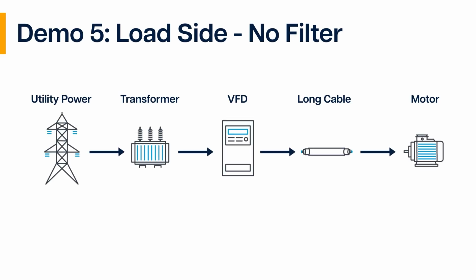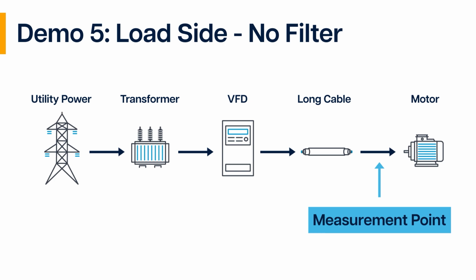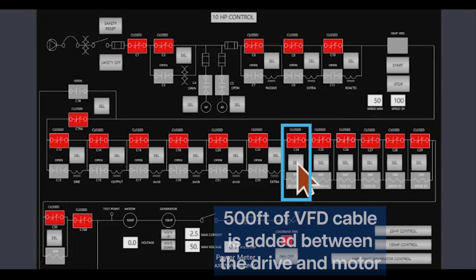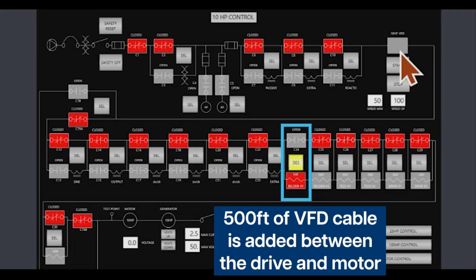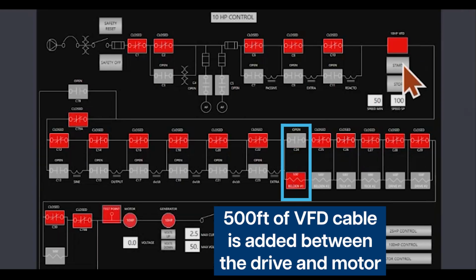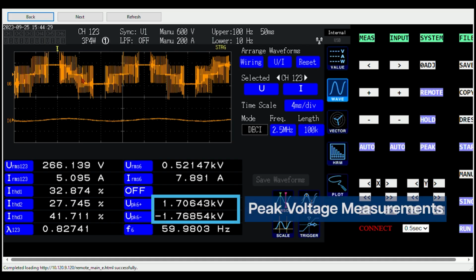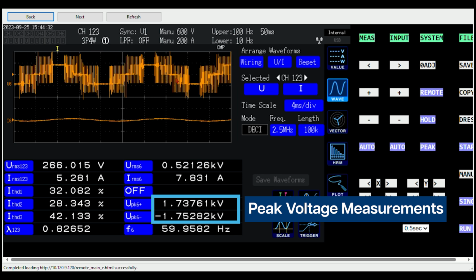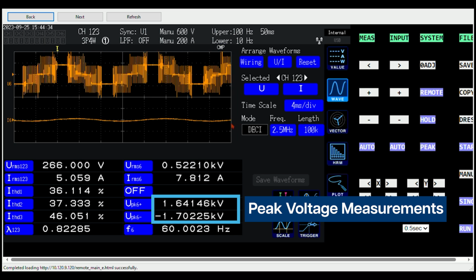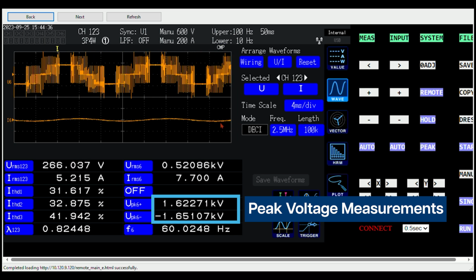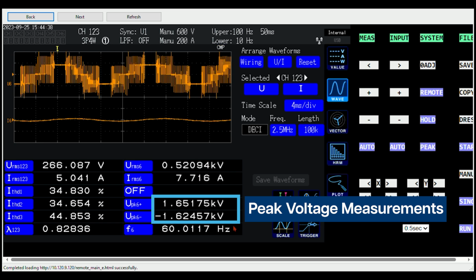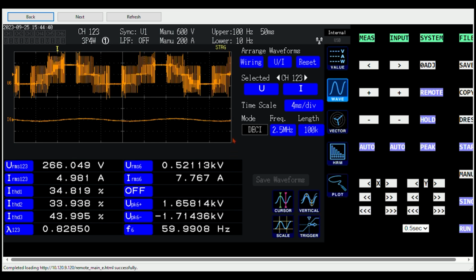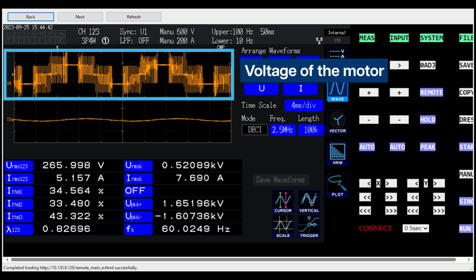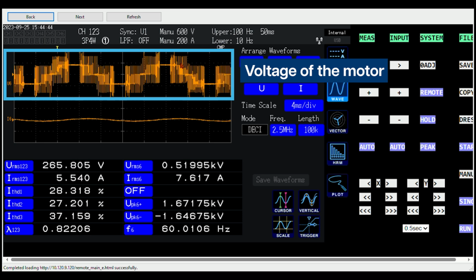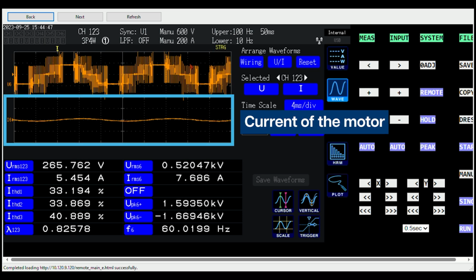Our load side demonstration begins with initial measurements at the motor input. We are using a 500 feet cable to connect the drive and motor. Observations reveal voltage peaks of approximately 1600 volts at the motor input. These peaks, reflecting back and forth along the cable, a phenomenon known as the reflected wave, can deteriorate motor insulation and damage the cables themselves.